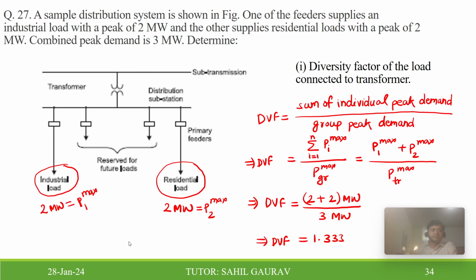So it is quite easy. We know that diversity factor is the ratio of the sum of individual peak demands divided by the group peak demand. So the individual peak demand is 2 plus 2, 4 megawatt, and the group peak demand is 3 megawatt. So you will get the diversity factor as 1.33.